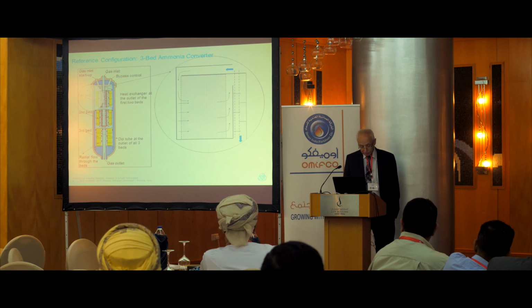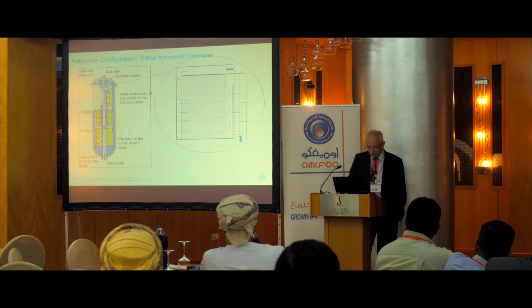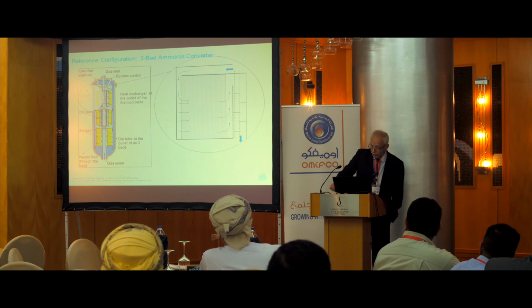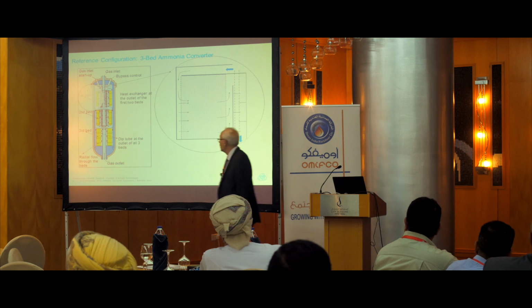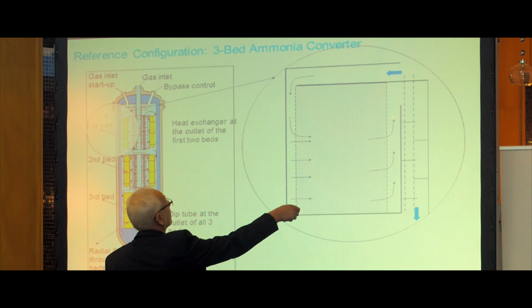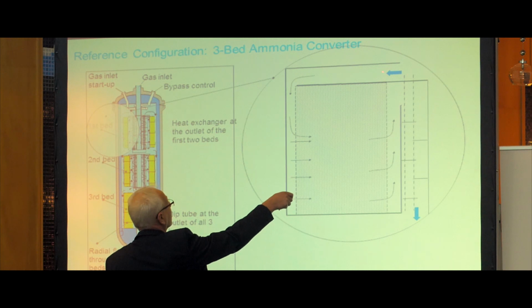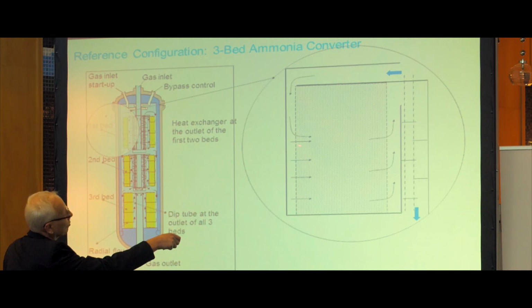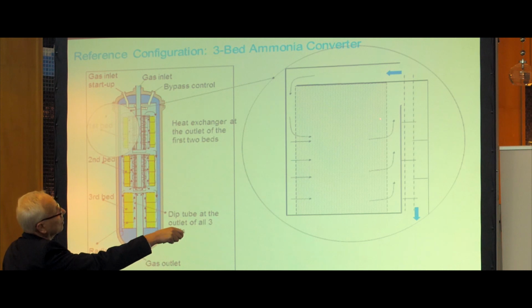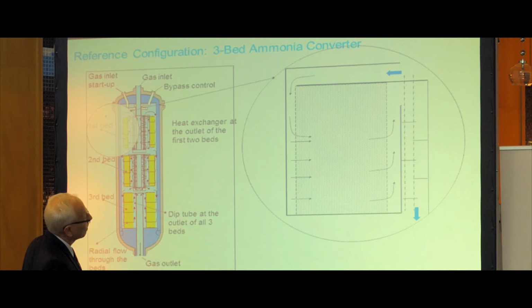How to optimize the existing volume inside an ammonia converter? Let's have a look at the non-optimized design. On the right side of this slide, you can see the first catalyst bed and an indication of the flow through the catalyst bed. It usually comes out of the tubes of an internal heat exchanger, passes through the catalyst bed, and then goes through a so-called dip tube to the shell side of the heat exchanger.